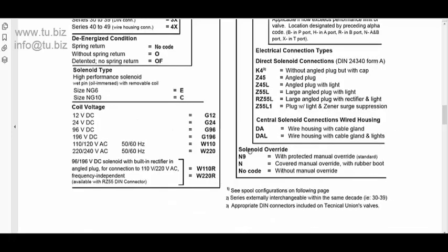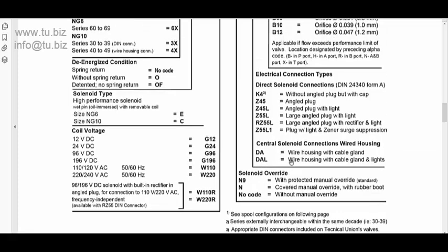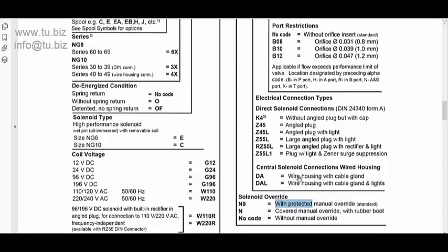Then you have the solenoid override option. You can either have it, or not have it, or have it covered, or uncovered. Those are the options that we offer. A lot of people will pick the N9, which is basically a manual override available, which is a button that you press, and the solenoid will shift. And people usually will want that, and will want it covered, so that nobody messes with it. But if you know it's there, you just uncover it, and you push it, and you use it.